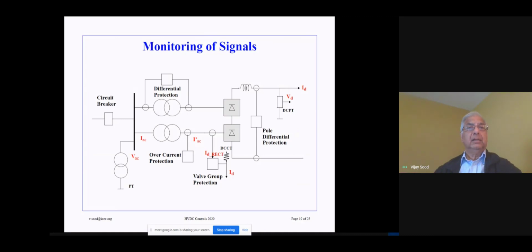So here, this graphic indicates the monitoring of the various signals, how they take place in a DC system. So here is an indication of the AC side, the AC bus, the transformers going into a 6-pulse bridge. This gives you a 12-pulse operation. So this could be a pole. The negative pole is not shown. So you can see over here, this is the DC side of the link. So we have a requirement to measure the DC voltage. So there's a DC PT, which will measure the voltage at the DC bus.